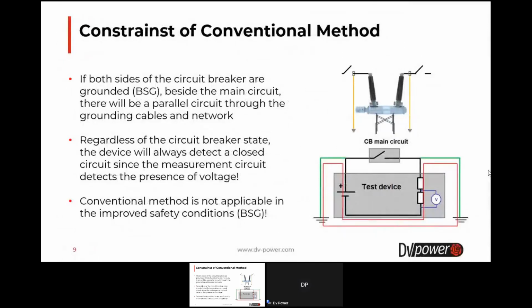What are the constraints of the conventional method regarding its application to measurement when both sides of the circuit breaker are grounded? If both sides of the circuit breaker are grounded, beside the main circuit there will be a parallel circuit through the grounding cables and network, as you can see in this figure. Regardless of the circuit breaker state, the device will always detect a closed circuit, since the measurement circuit always detects the presence of voltage. That means the device will not be able to detect a change of the circuit breaker contact state. So the conventional timing method is not applicable in the improved safety conditions.